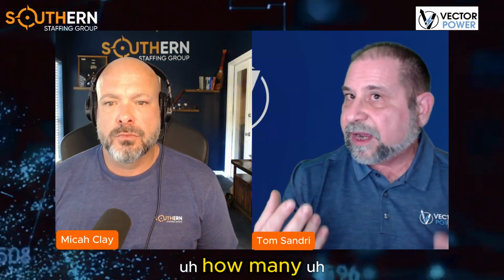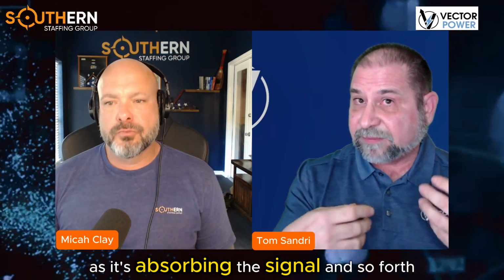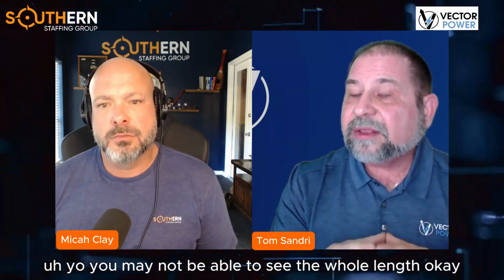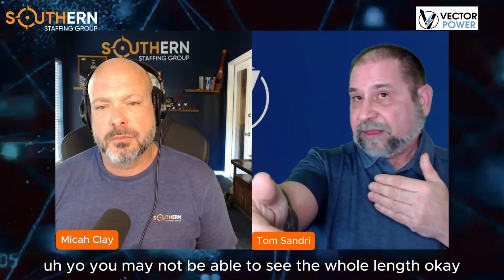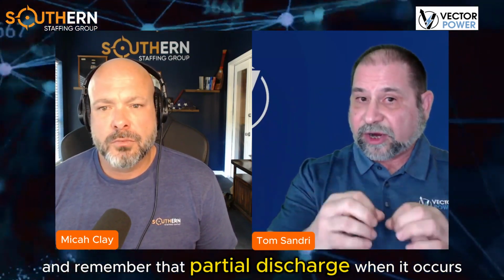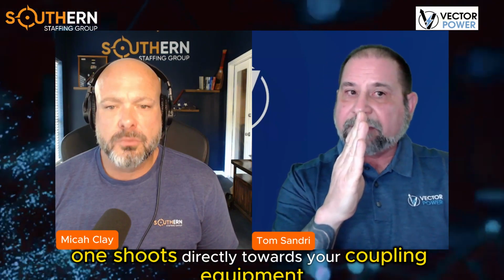So with attenuation, depending upon the length of the cable and how many splices and everything may be there as it's absorbing this signal, you may not be able to see the whole length. And remember that partial discharge, when it occurs, pop, the transient shoots both directions. One shoots directly toward your coupling equipment and passes it at time period 1. The other pulse fires off toward the other end, reflects off the end of the cable, and now has to have enough energy to make its way all the way back to the receiver. If it attenuates and burns out, you can't do mapping because you don't have the two pulses any longer.